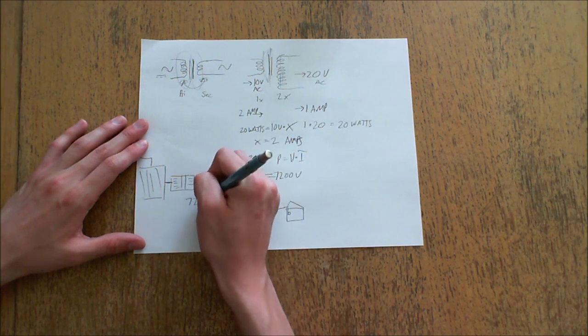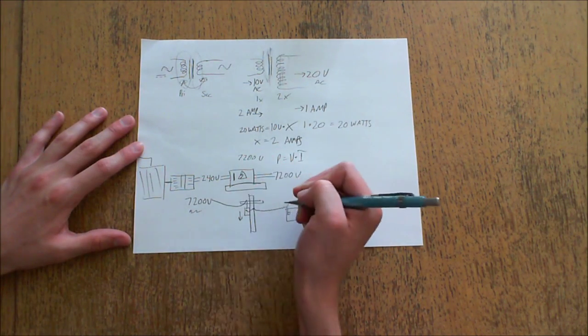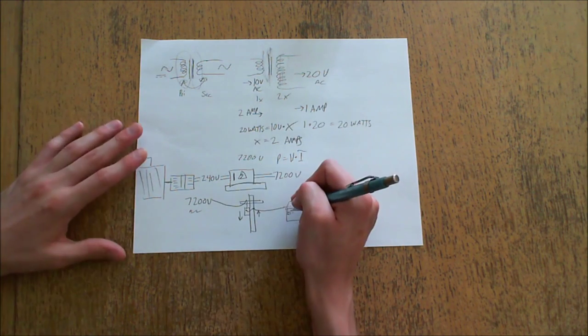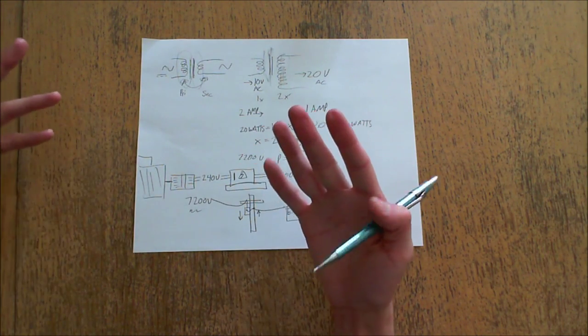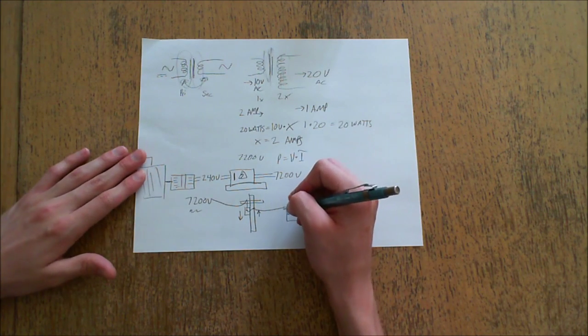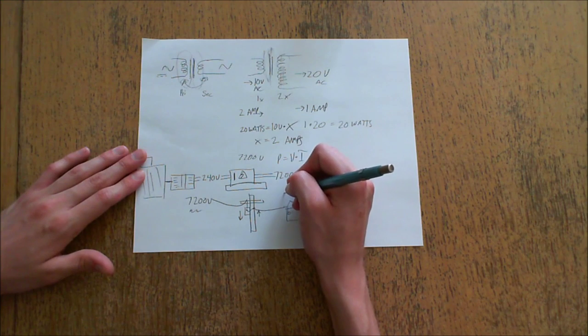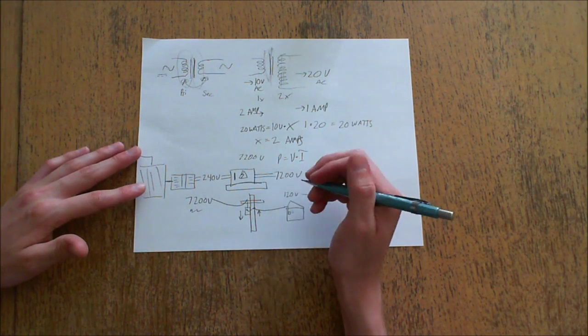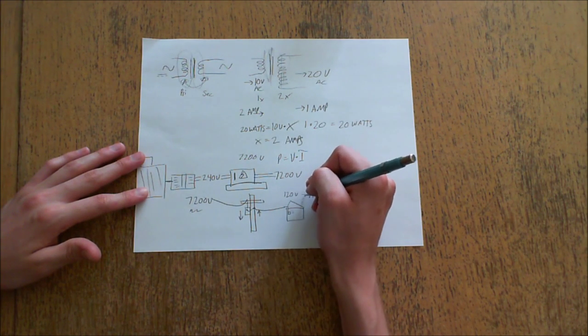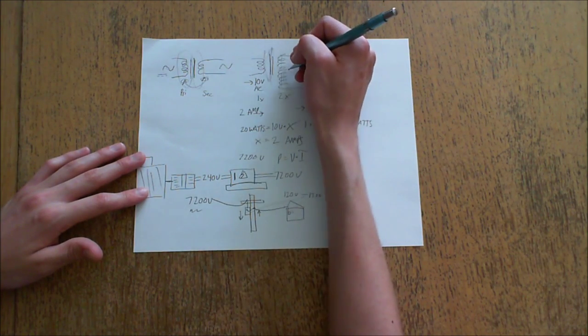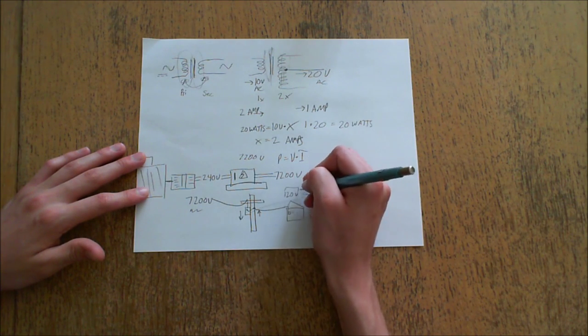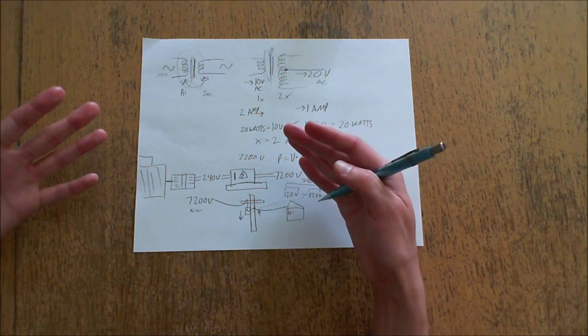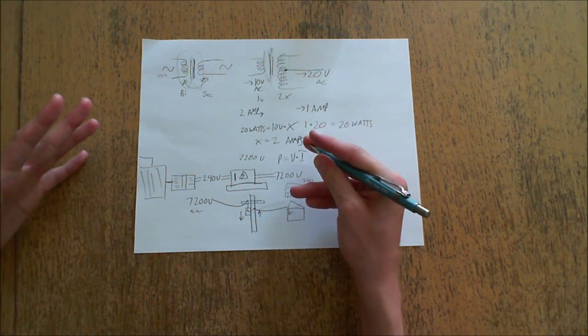You also might be familiar with the kind that's on top of a telephone pole mounted to the side of it, usually connected with cables that go to your house and to your electrical panel. This does the same thing, except it takes the 7200 volts or whatever it is and drops the voltage at the expense of increasing the current, which is what you want for your house because you don't want extremely high voltage. 7200 volts at your outlet would potentially jump out, potentially short across wires, and your electronics aren't designed to run on that either. You end up transforming this down to a split circuit of 120 volts and another 120 volts. This is called split single phase. Since these are from a center tap on the transformer, you get 120 volts on each side, which lets you run 240 volts for the big stuff like your air conditioner, heat pump, dryer, all that kind of stuff.